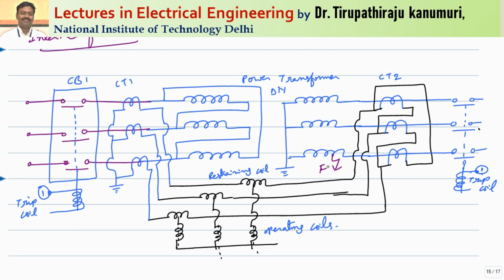So because of this fault, how is this going to be affected? Whenever this internal fault happens, this fault current is not passing through your relay because it is closing like this and returning back. Agree with me? As the fault current is only closing itself, this will not pass through this circuit breaker. But this fault current will be supplied by the corresponding circuit in the primary side. So this fault current is supplied by this.